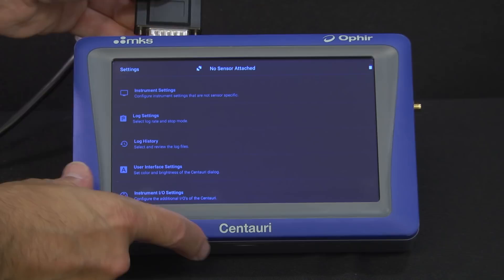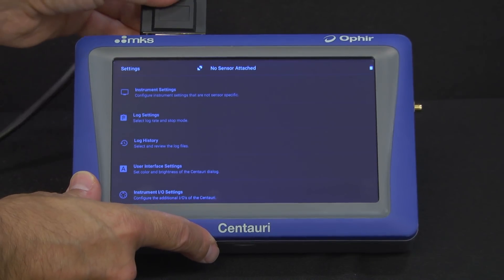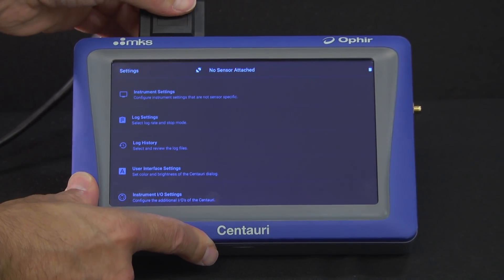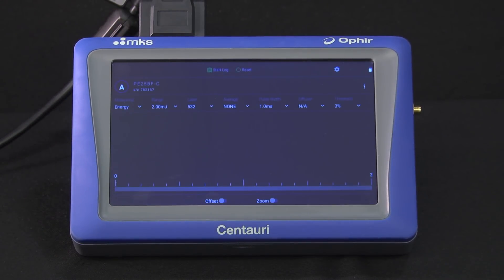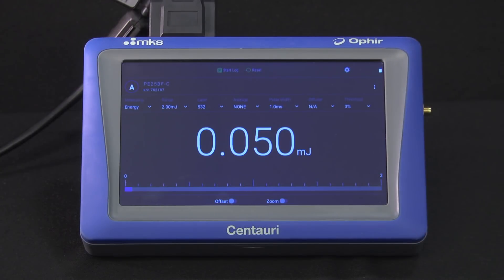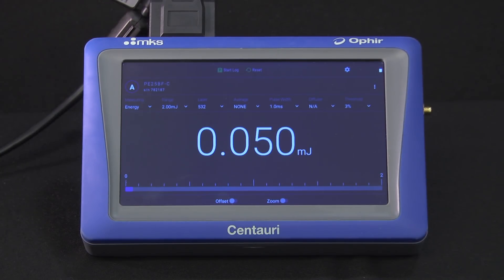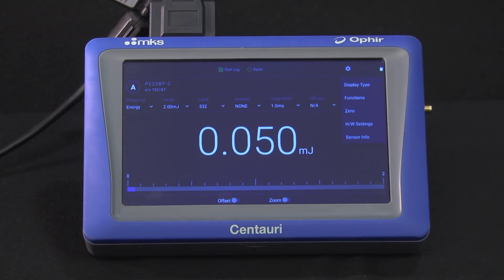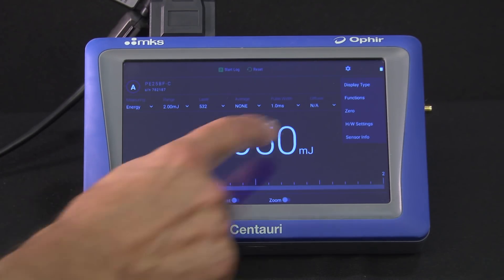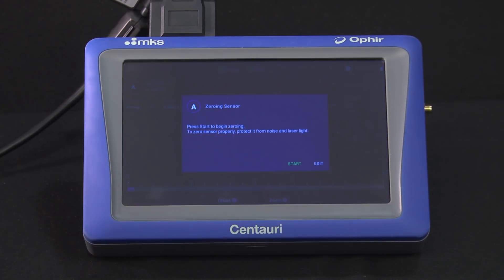We'll now connect a pyroelectric sensor, used for measuring energy per pulse of a repetitively pulsed beam. For the most accurate reading when using a pyroelectric sensor with any Ophir meter, we recommend that you perform zeroing with the meter and the specific sensor connected.